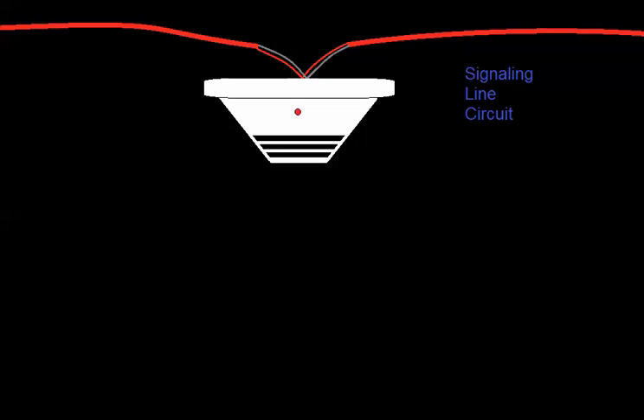As a programmer, when you program these panels, you can set the sensitivity of the detector. It will set a threshold so that a certain percentage of smoke would not be an alarm for one detector, but for another detector that same amount might trigger an alarm. For example, near a high-traffic main entrance you don't want it to be very sensitive because there's going to be a lot of dust, whereas in a server room or a clean environment where it's important to get the alarm signal as soon as possible, you would set it for higher sensitivity.